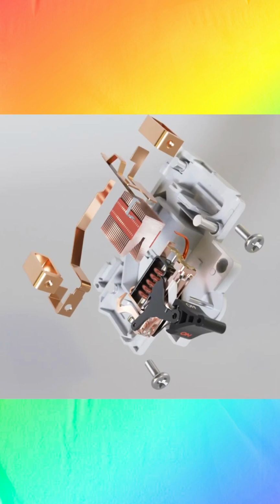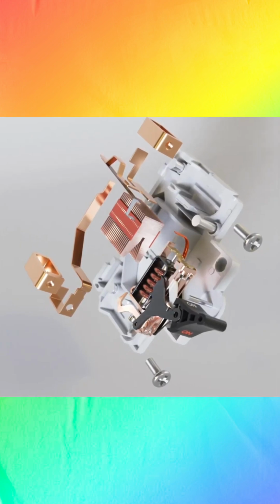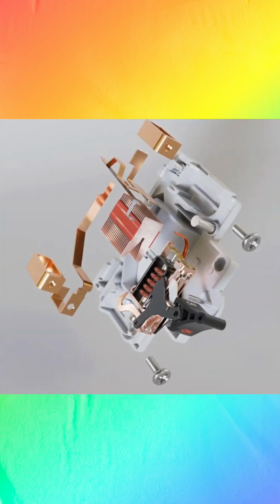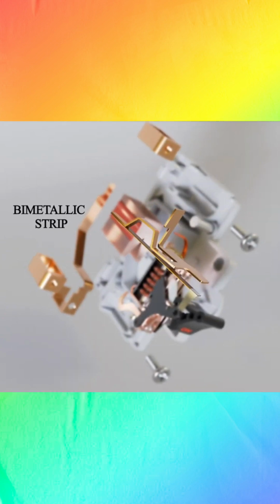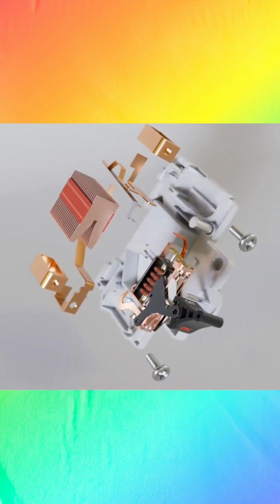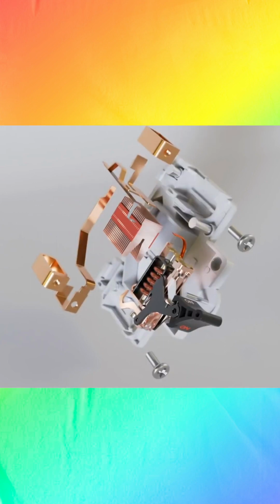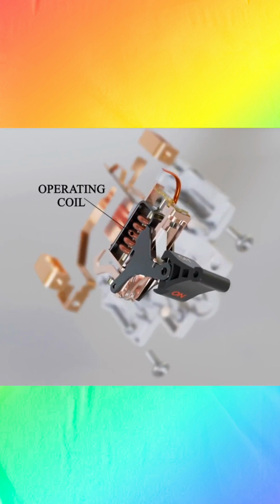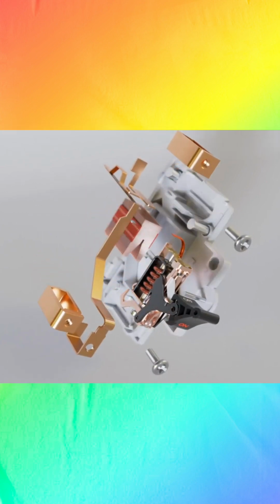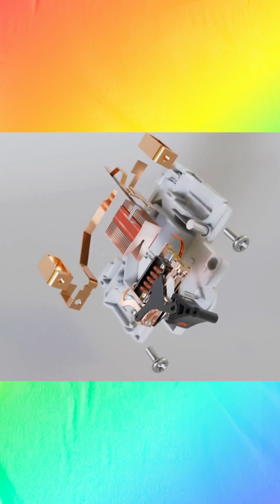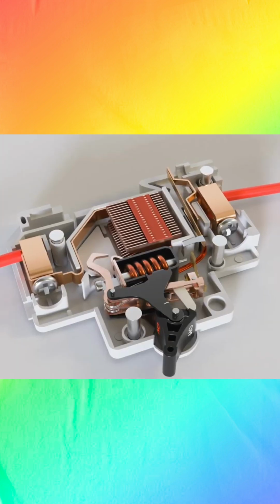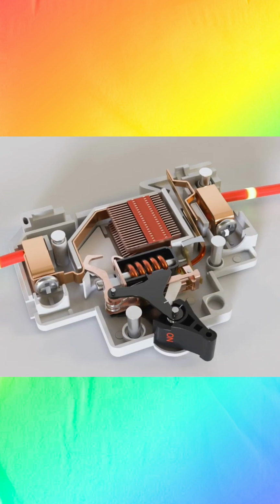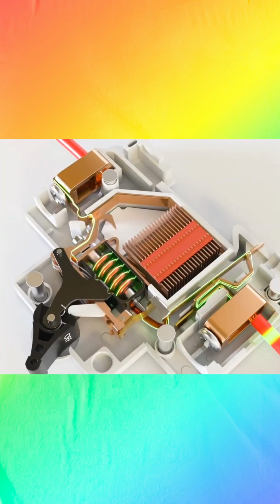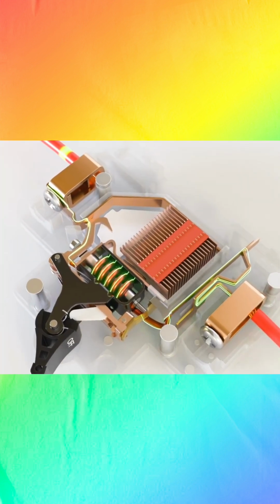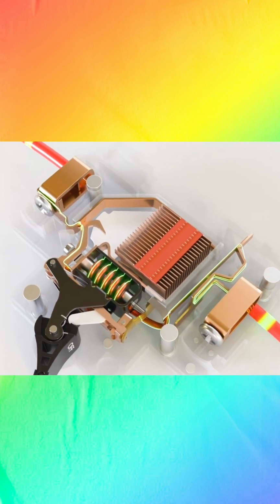The internal structure of an MCB can be divided into four main sections. First section consists of bimetallic strips. Second section is the arc chamber. Third section contains the electromagnetic coil and operating mechanism. And the fourth one houses the connectors. As we discussed earlier, an MCB is always connected in series with the phase wire. In an MCB, load current flows through bimetallic strips and the electromagnetic coil.